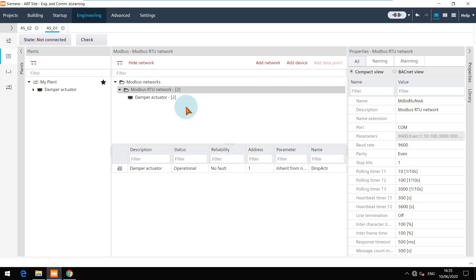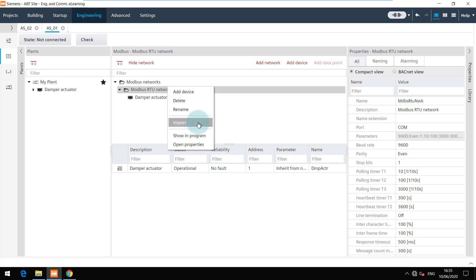In ABT Site, most of the properties of the device are mapped. The result is a configurable third-party Modbus device. To begin, right-click on the Modbus network and choose import option. If you import a TCP/IP template on RTU network or otherwise, the tool will give the relevant error message.